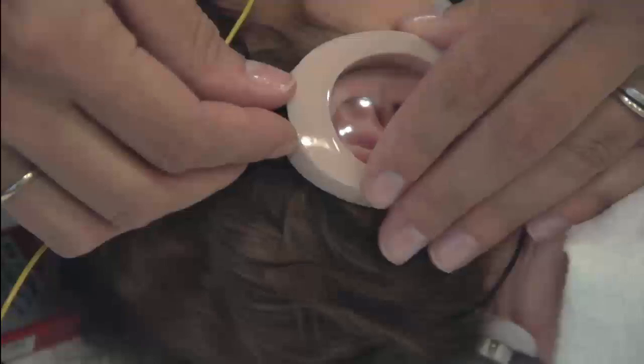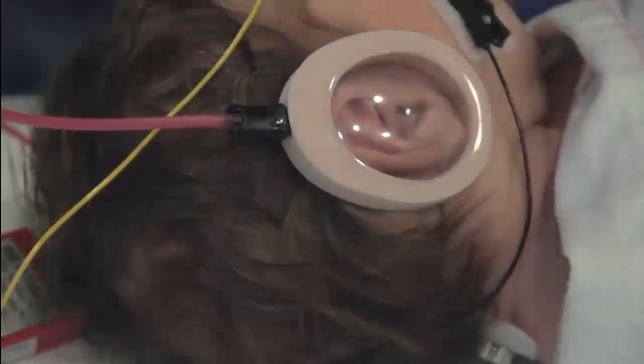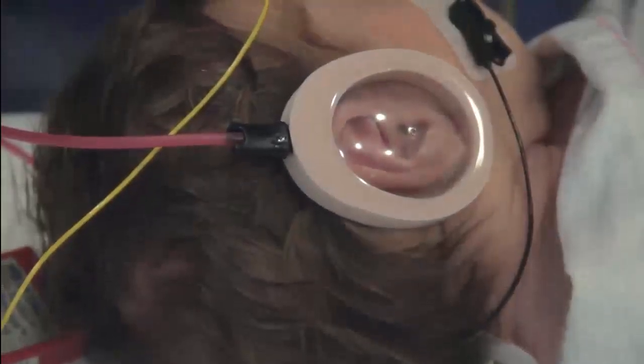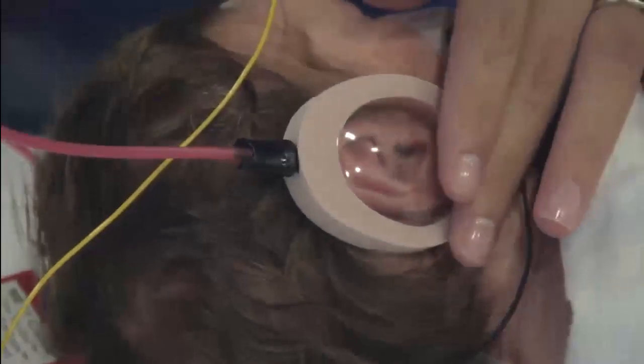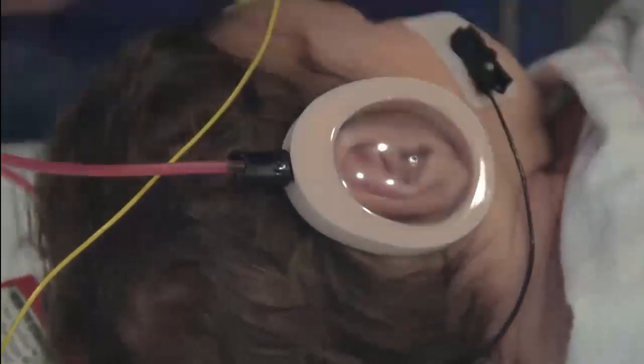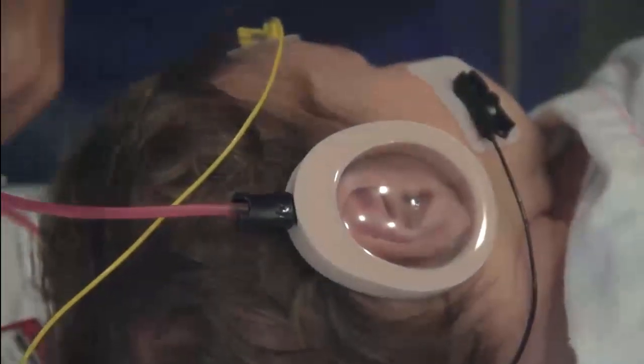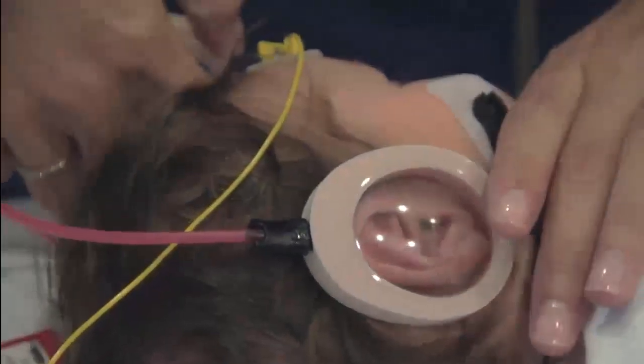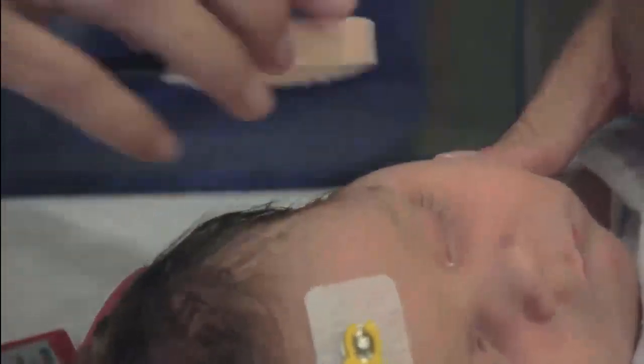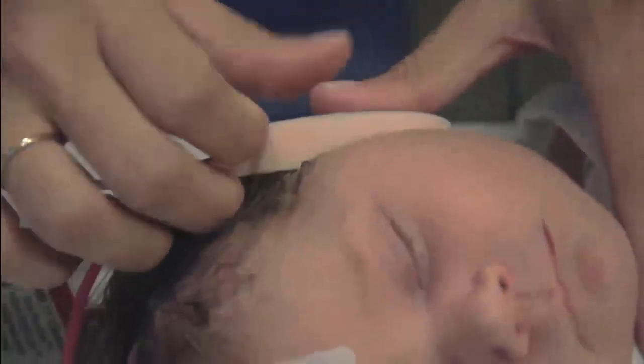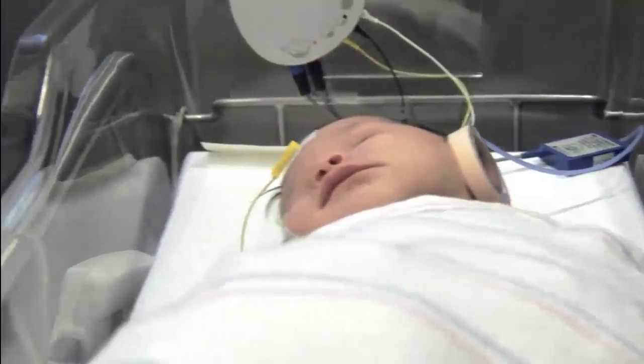Looking through the clear cover on the ear cup, position it around the baby's ear with the adapter pointing toward the top of the baby's head. Press gently around the perimeter of the ear cup so that it sticks to the baby's skin. Repeat this process for the opposite ear. Use of the ear cups makes it possible to screen both ears at the same time. When the baby is prepped, start the measurement.